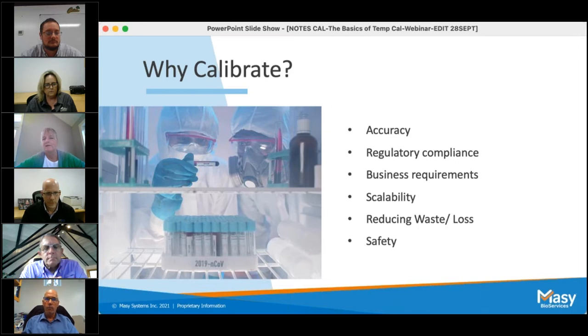If someone's asking about the temperature outside, that does not require accuracy. It's either warm, hot, or cold, etc. But in the pharma world, with some vaccines, if the temperature goes below 0 degrees C, then the vaccine becomes ineffective. So calibrations in part allow the consumer to take medications with the assurance that they are safe and effective. Required for medicine, sorry, I'm going to turn it over to you, John.